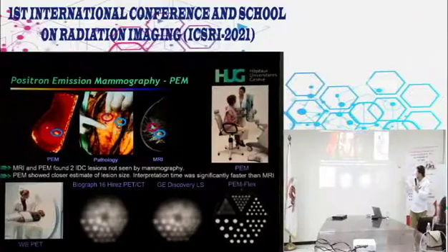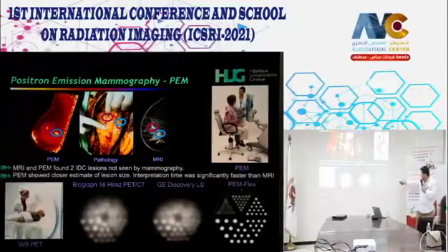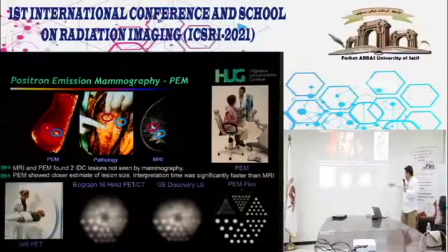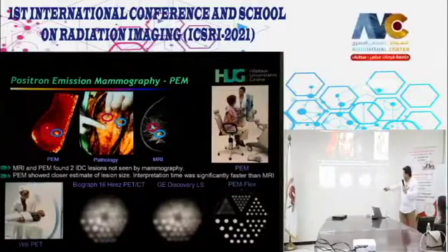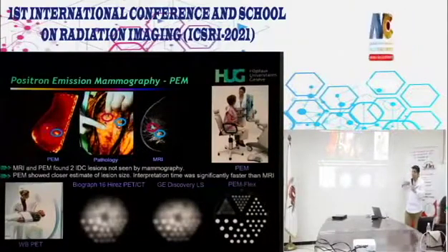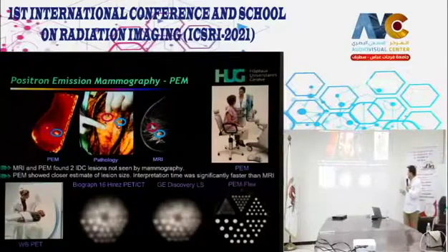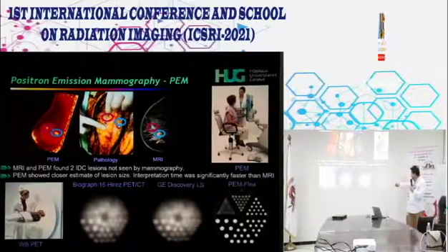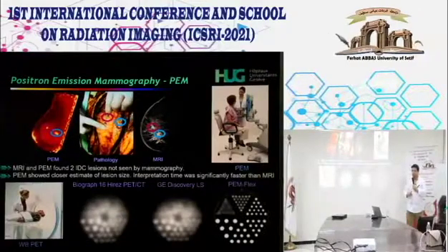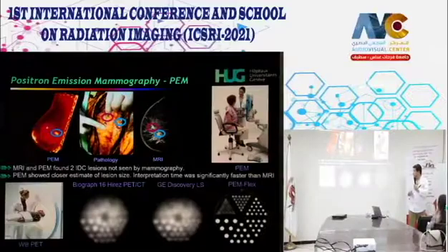And with this type of design, so you see basically when you scan the Derenzo phantom, which has basically rods giving you some different spatial resolutions, and then you can appreciate the comparison between the system dedicated for whole body imaging, having spatial resolution close to 4 millimeters, with the system designed specifically for mammography with a very high spatial resolution, so you can depict basically resolution of 1.6 millimeters, and this improves the detectability of small lesions.